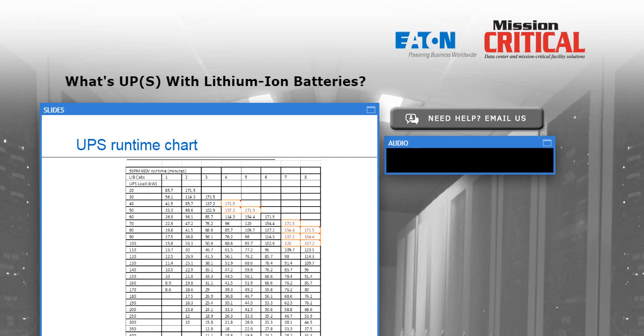Well, you can do that, but it turns out that if I try to do it with a minimum number of cabinets, the discharge is so intense that the temperature rises too quickly and the battery will automatically disconnect itself. So if I need a 5-minute discharge, I probably would need to buy about 8 minutes worth of battery in order to make sure I can do that short of a discharge at that high current without over temperature.